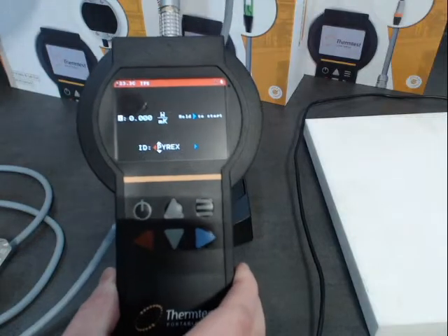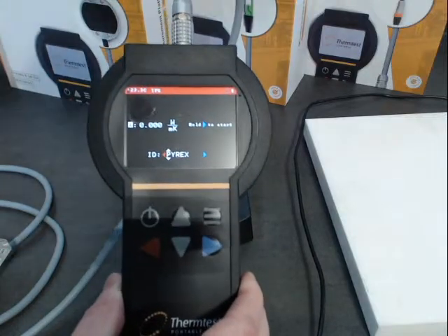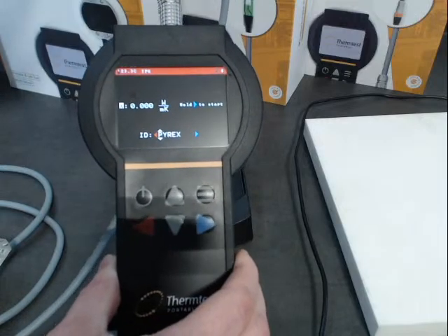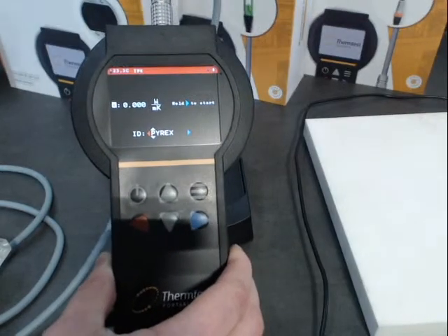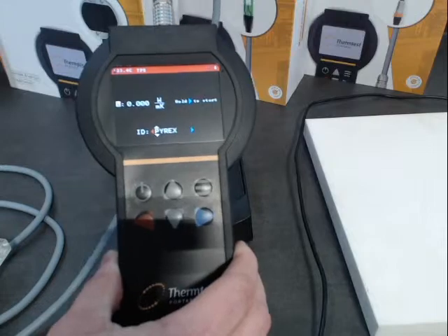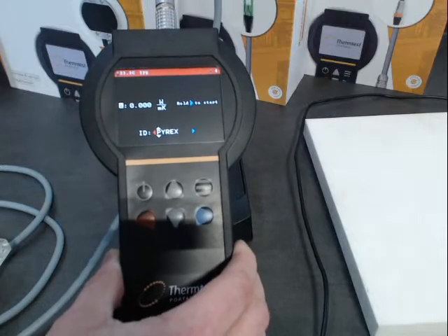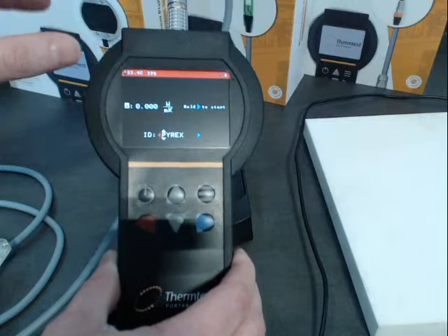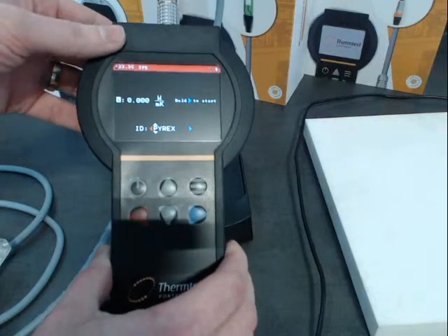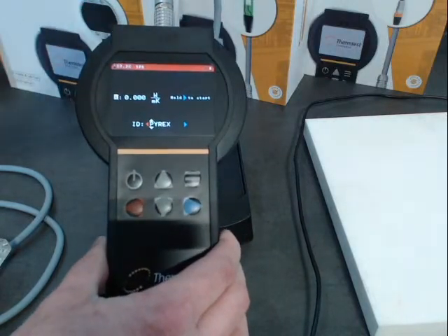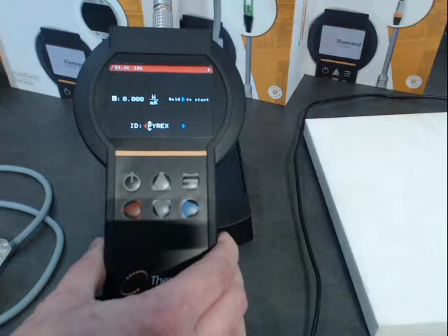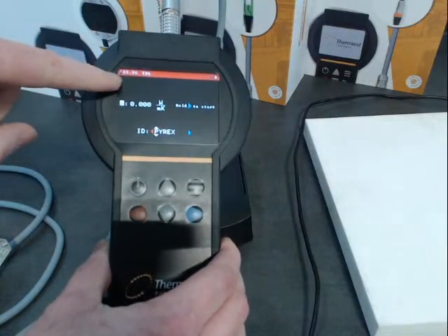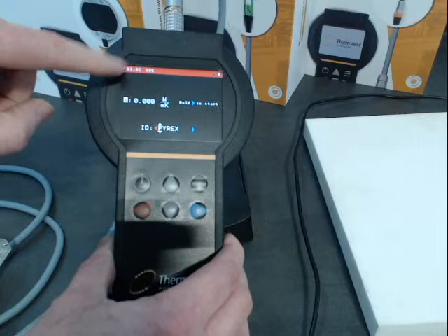Generally the TPS and the THW sensors available for this are good from 10 to 40 degrees Celsius as environment temperatures. The other units we have go from cryogenic up to 300 or 400°C. So this is meant to be a portable, easy-to-use instrument with ranges that are more narrow, and that really comes from the construction of the sensor.